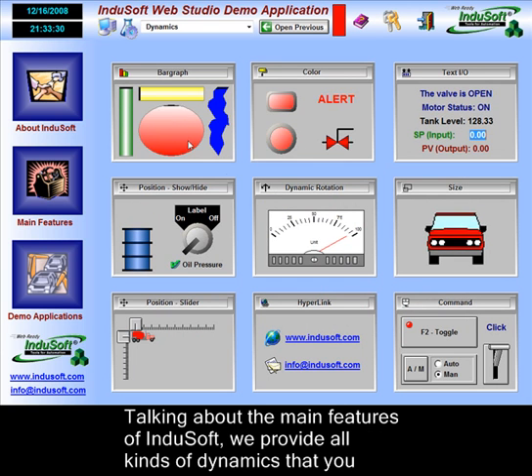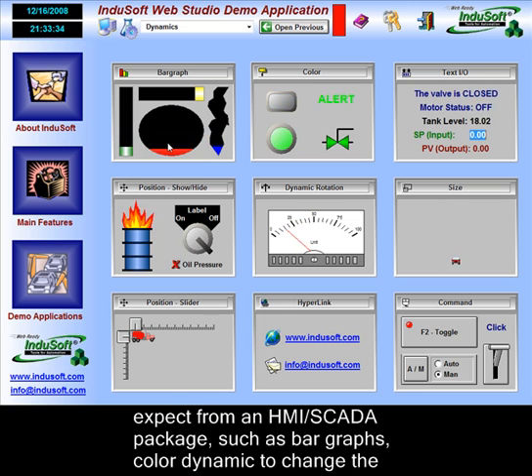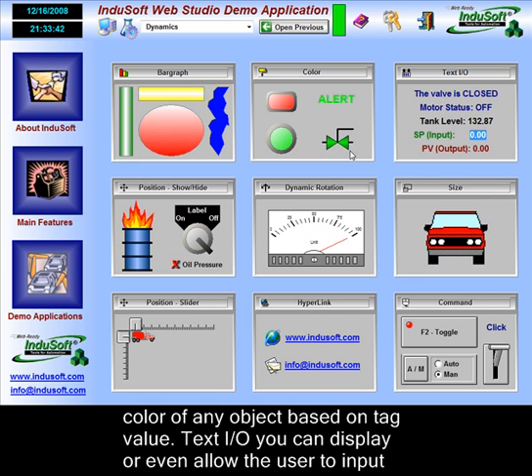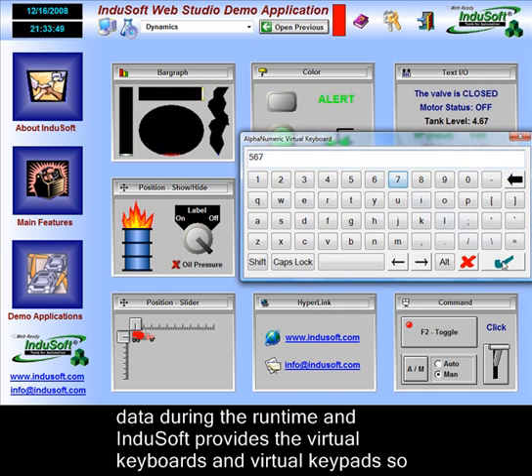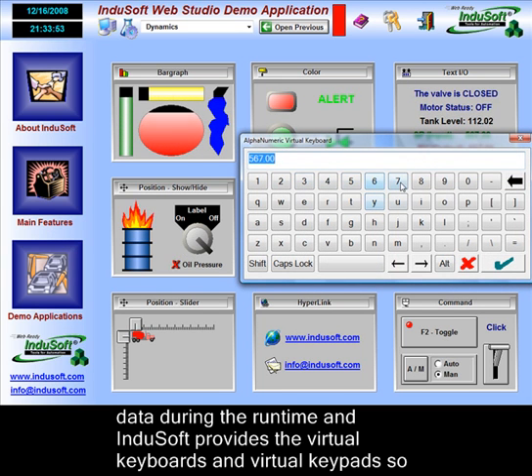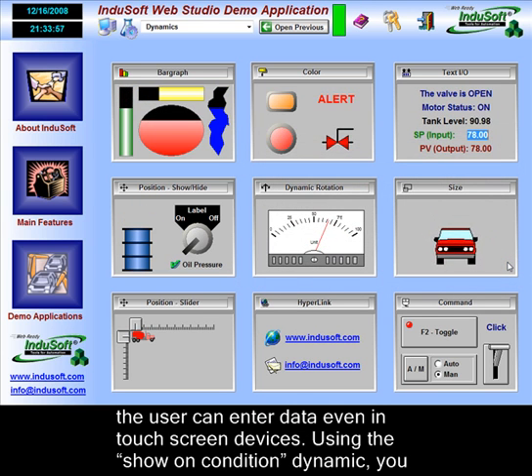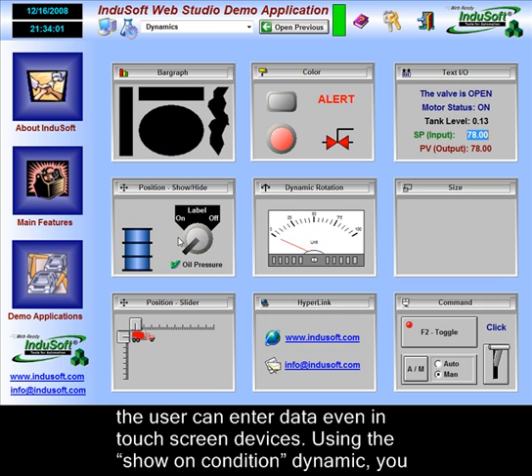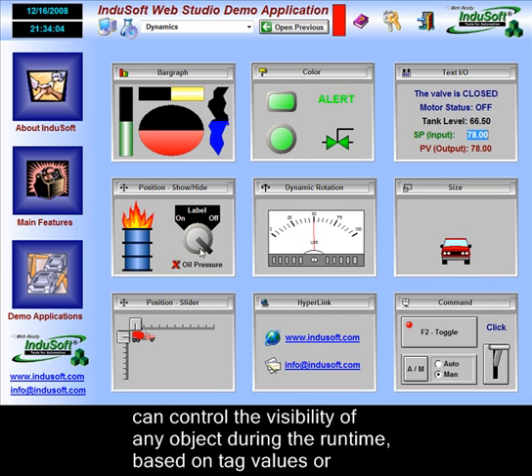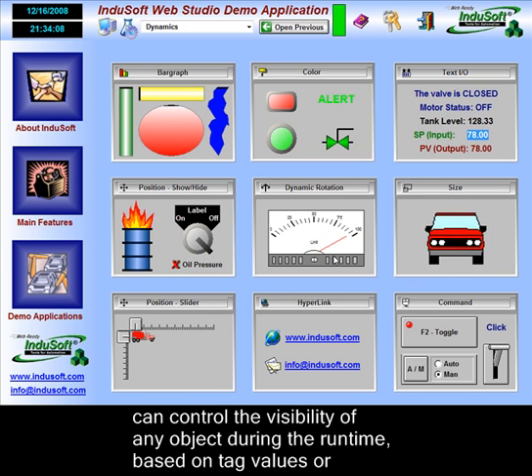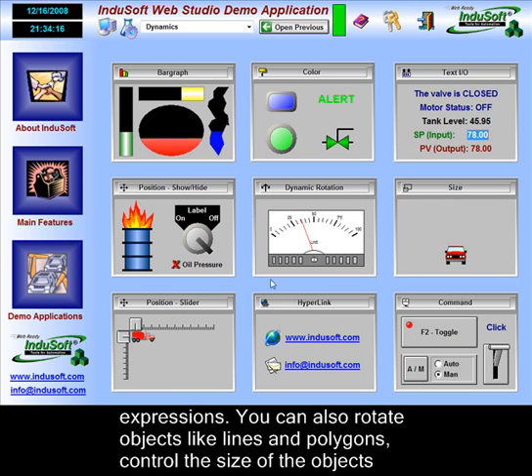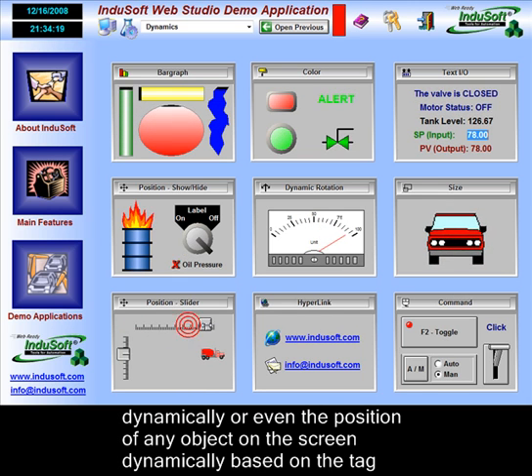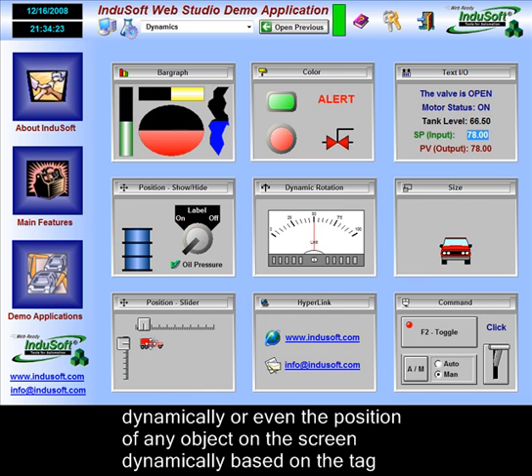Talking about the main features of Indusoft, we provide all kinds of dynamics that you expect from an HMI/SCADA package, such as bar graphs, color dynamic — to change the color of any object based on a tag value — text I/O, where you can display or allow the user to input data during the runtime. Indusoft provides virtual keyboards and virtual keypads for entering data even on touch screen devices. Using the show-on-condition dynamic, you can control the visibility of any object during runtime based on tag values or expressions. You can also rotate objects like lines and polygons, and control the size or position of any object on the screen dynamically based on tag values.